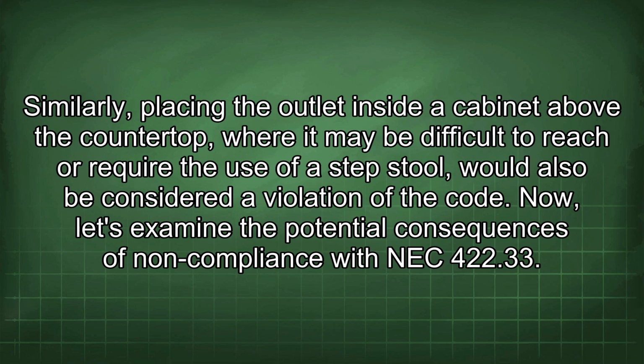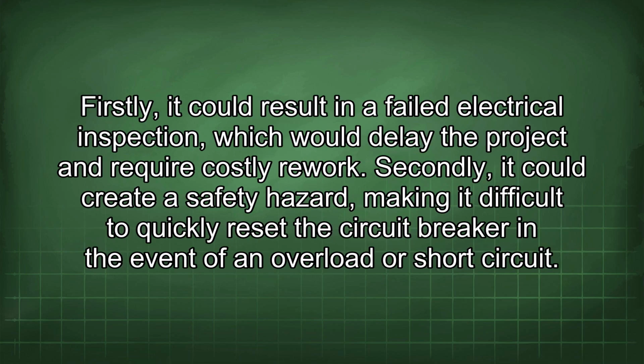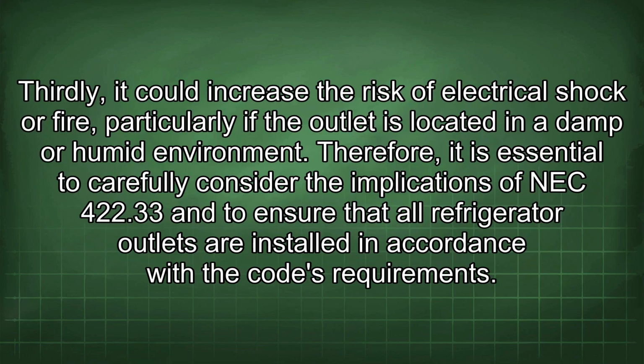Now let's examine the potential consequences of non-compliance with NEC 422.33. Firstly, it could result in a failed electrical inspection, which would delay the project and require costly rework. Secondly, it could create a safety hazard, making it difficult to quickly reset the circuit breaker in the event of an overload or short circuit. Thirdly, it could increase the risk of electrical shock or fire, particularly if the outlet is located in a damp or humid environment. Therefore, it is essential to carefully consider the implications of NEC 422.33 and to ensure that all refrigerator outlets are installed in accordance with the code's requirements.